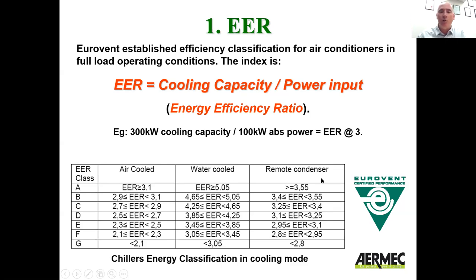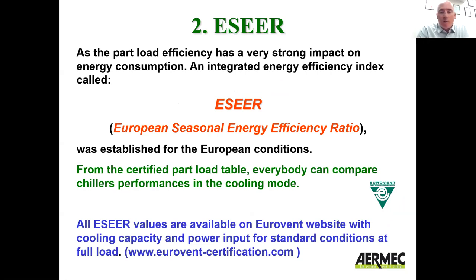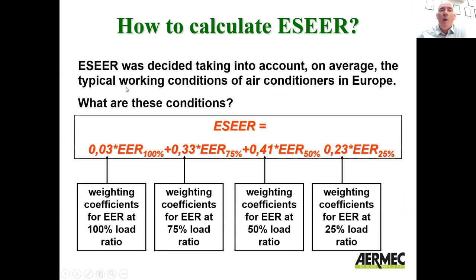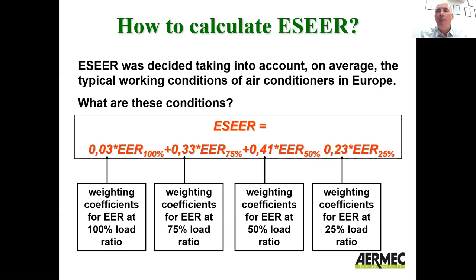So your air-cooled, your water-cooled, your remote condenser with a condenserless unit. But we rarely run at 100% load, so your European Seasonal Energy Efficiency Ratio is more important, particularly for HVAC applications, because they're ramping up and down throughout the year to suit the load. This is what's called a weighted formula. We assume that the chiller will run at 100% load for only 3% of the year, 75% load for 33% of the year, 50% load for 41% of the year, and 25% load for 23% of the year. All manufacturers have to submit their energy efficiency ratio using this formula, and therefore you get an independently verified classification from Eurovent.